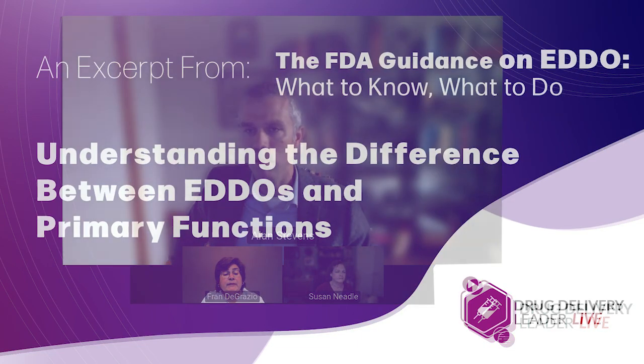The other is where risk comes into the identification, or into the overall process. So you're filtering things out of being primary functions based on risk, whereas EDDOs are inherent to the design features. And then the risk comes into what type of design verification, or how much design verification, or what my control strategy needs to look like. That would be where the risk would be.